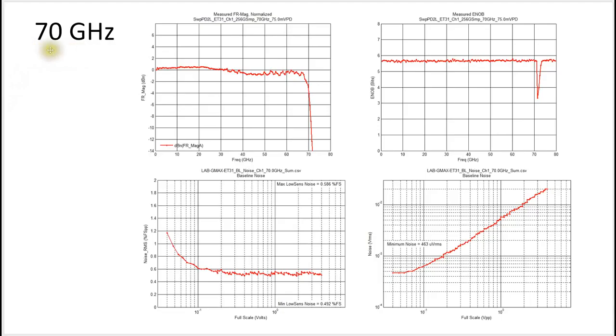Now here the instrument is set to a bandwidth of 70 gigahertz. And at this bandwidth, they're trying to measure the flatness of the front-end response as well as the effective number of bits and noise and some of the other measurements. Now, if you look here, you can see how flat the frequency response is. I mean, this is within plus or minus 0.75 dB or so, all the way to 70 gigahertz, which is the 3 dB bandwidth of the instrument. And this is not even the final version. It's very difficult to accomplish this.